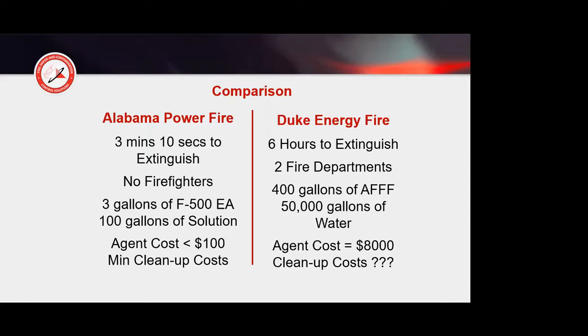This was in 2018, I believe. This is just a quick comparison. I actually have a separate PowerPoint for this comparison, but Alabama Power, they have an F500 CCS system in place. They had a fire. They caught the fire on the transformer on their security cameras that's attached to their smokestack, and it took 3 minutes and 10 seconds to extinguish.